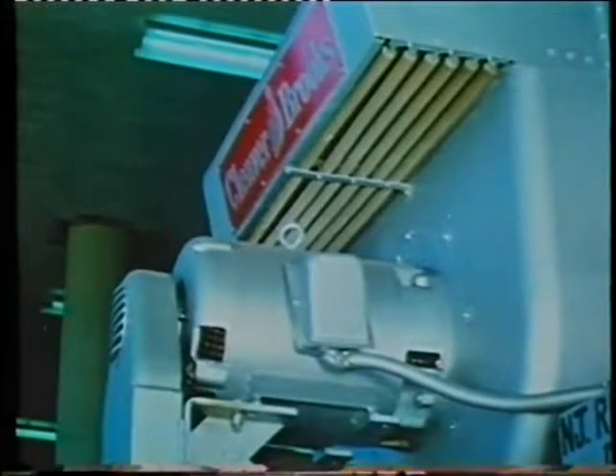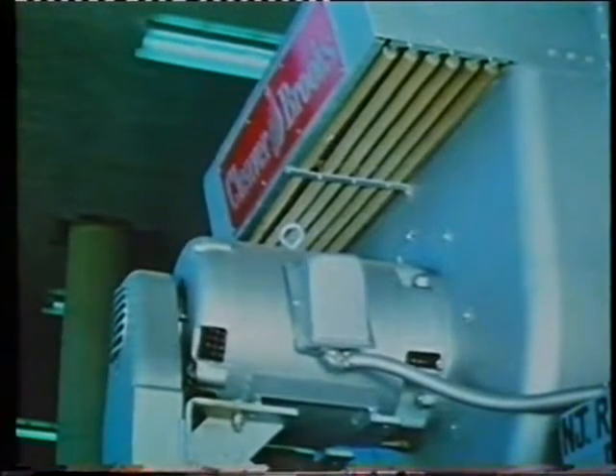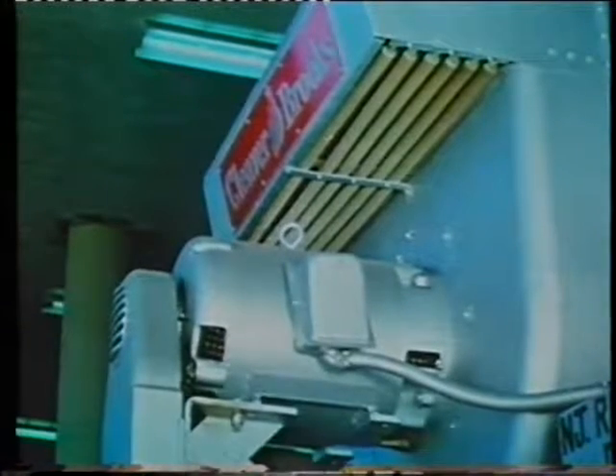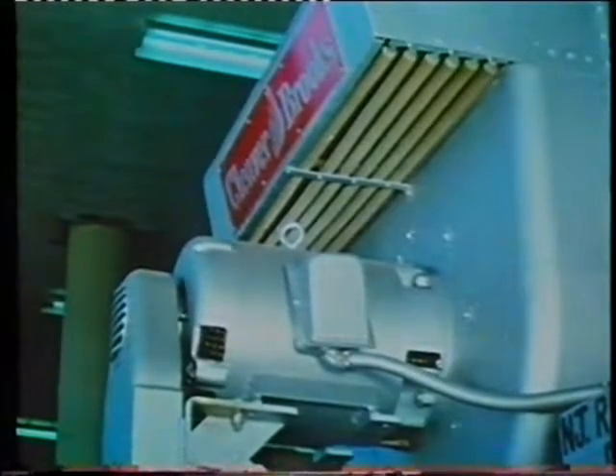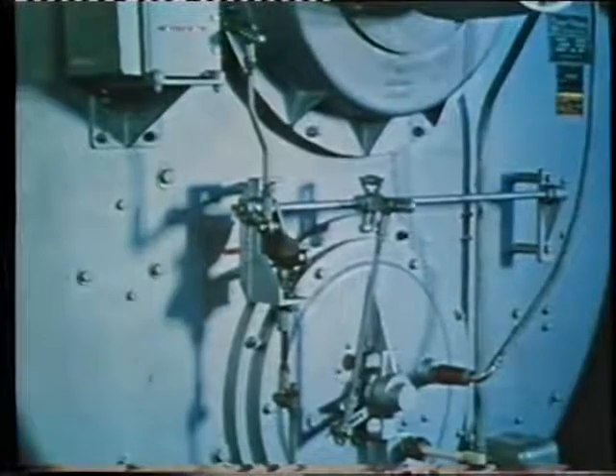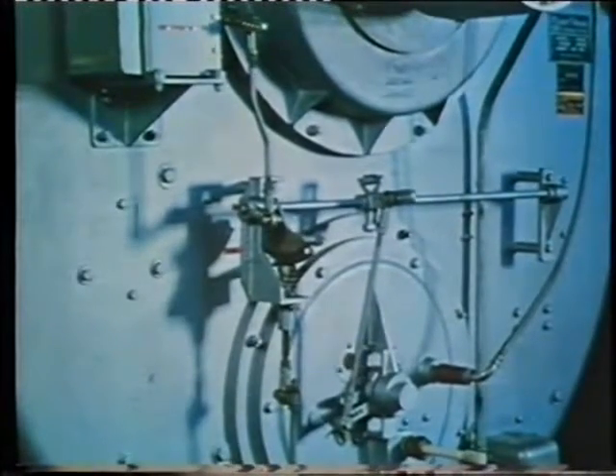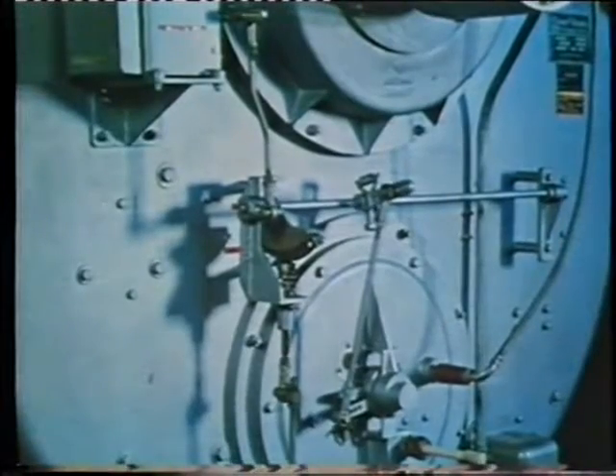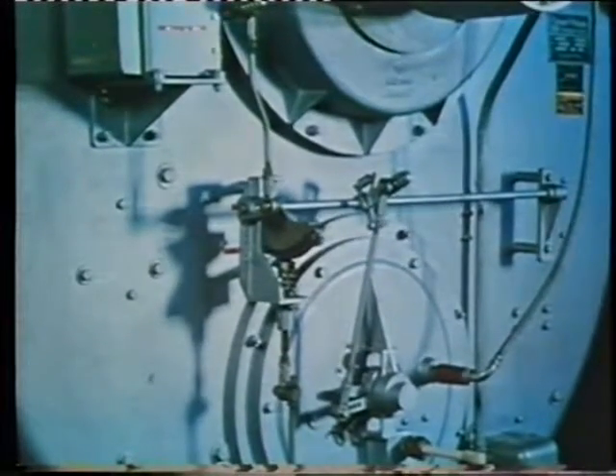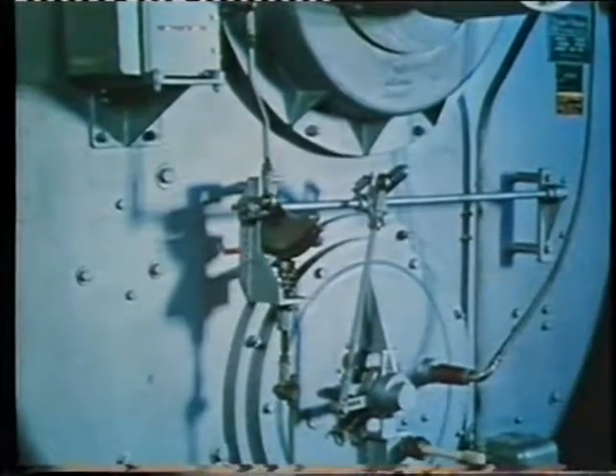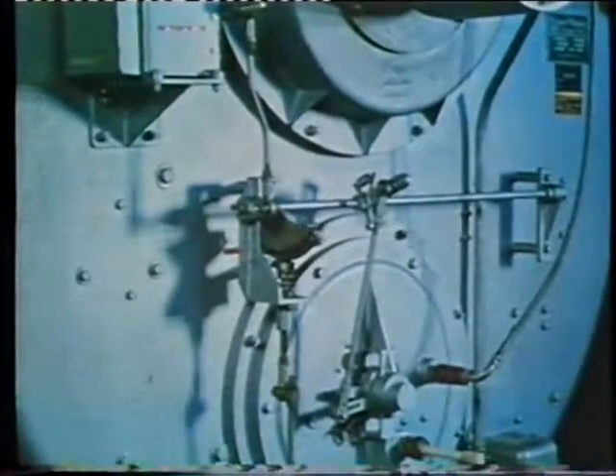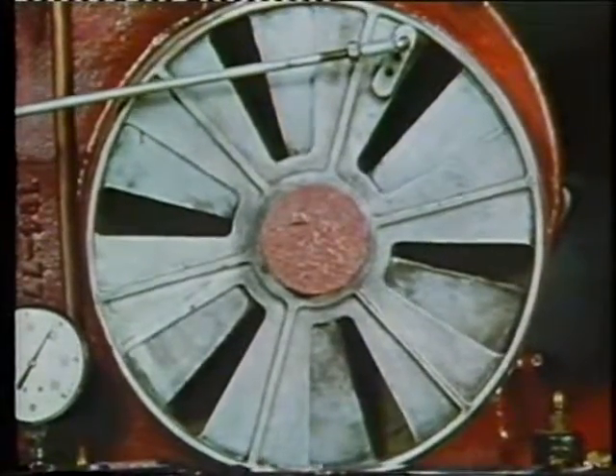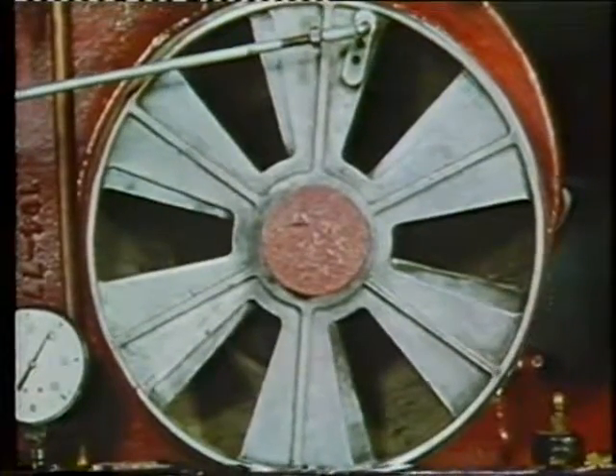In a forced draft system, a blower on the front of the boiler forces air into the intake located just above the motor. On an induced draft boiler, the fan would be located in a stack and would pull air into the combustion chamber rather than push it. On most boilers today, the control of the draft, as well as the fuel supply and the fuel-air ratio, is automatic. The draft control linkages on the front of the boiler are driven by the modulating motor in response to signals from the programmer. Movable shutters on the damper, operated by the linkage, control the amount of air that will be allowed to enter the burner.